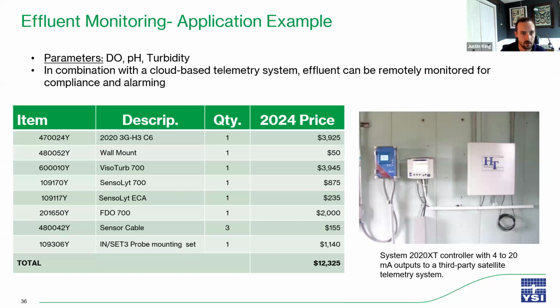And then finally, we will talk about effluent monitoring. This is an example of a system where a wastewater plant is measuring DO and pH as well as turbidity for compliance assurance. These 3 probes were installed into a flow-through mounting set, and they were set to alarm and alert the operators as soon as any of those parameters went outside of the permitted range.